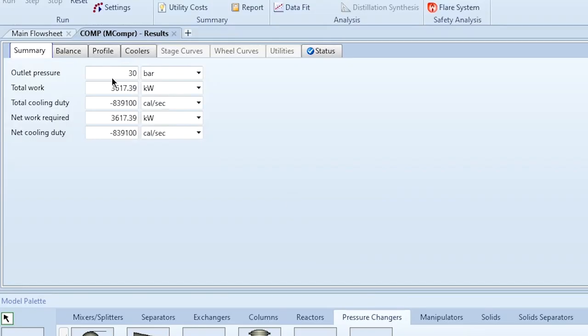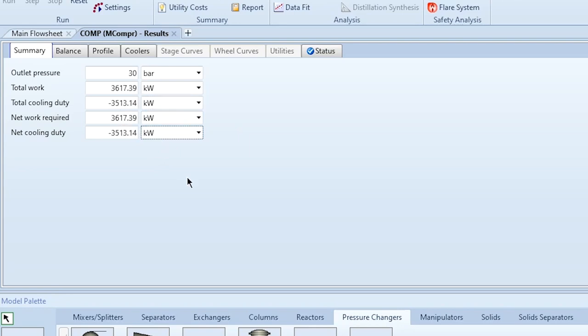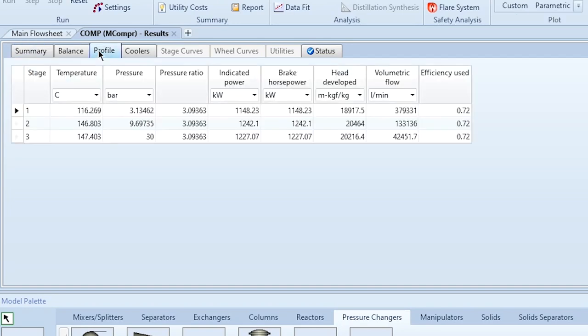Going to Compression Results, the outlet pressure is 30 bar. Total work for all three compressors is 3617 kW. Total cooling duty for all coolers — two intercoolers and one after-cooler for the three-stage system — is 3513.14 kW. Net work and net cooling duty remain the same since we assume no heat leak or pressure drop.